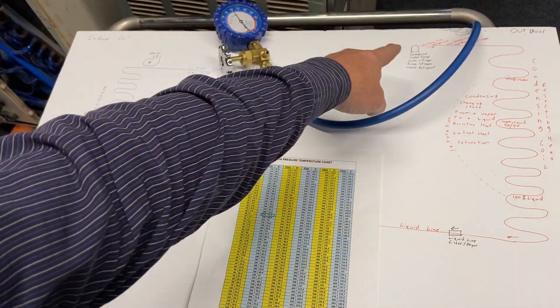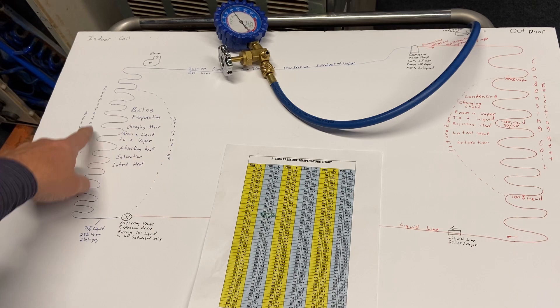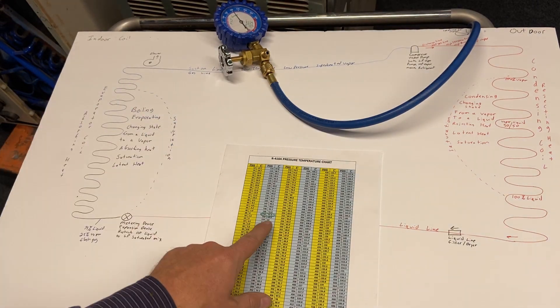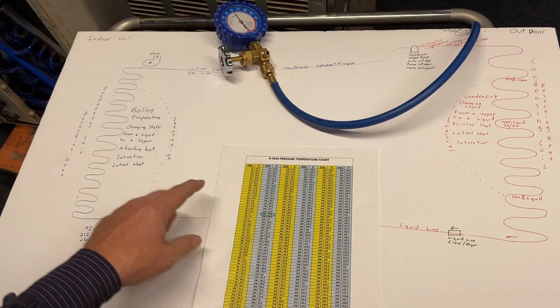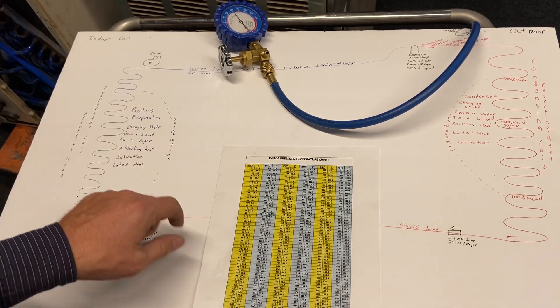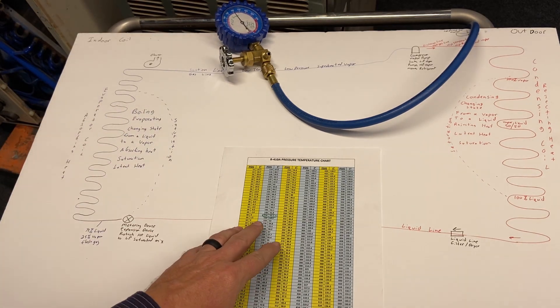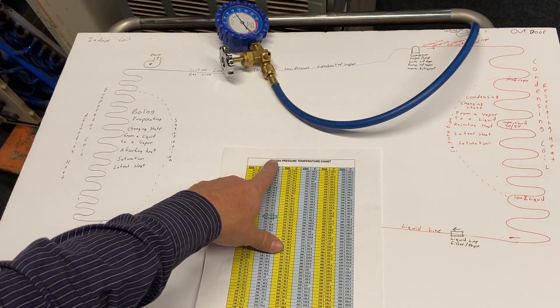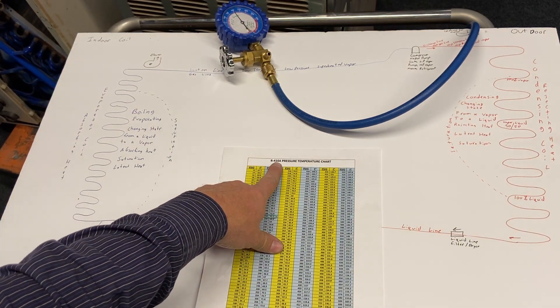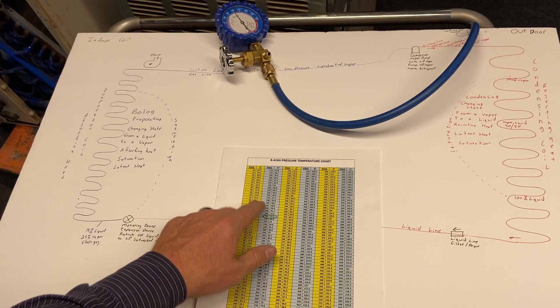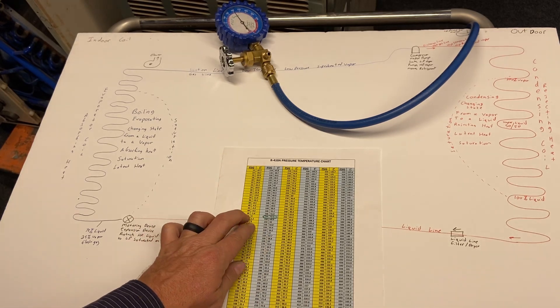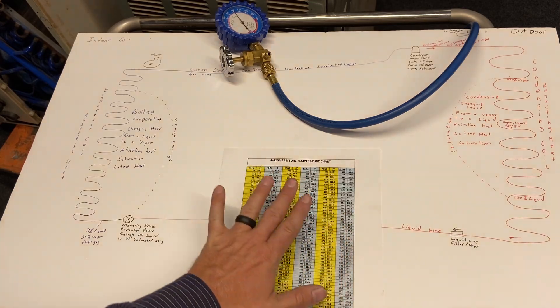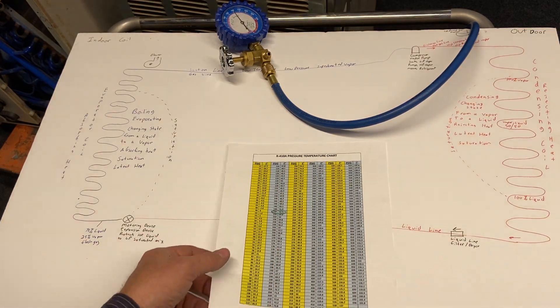I want you to understand how to read one of these pressure-temperature charts. That pressure, even though I'm taking it outside, represents my saturated temperature — my boiling or evaporation temperature inside. That's the key number. I'll try to put a link in the video for where these charts are. This simple single-refrigerant chart I like because it just shows pressure and temperature paired together all the way through — quite simple to work with.